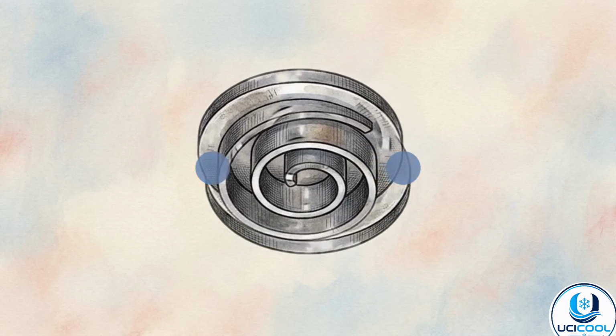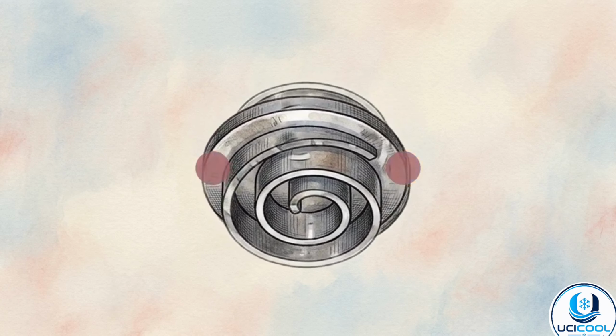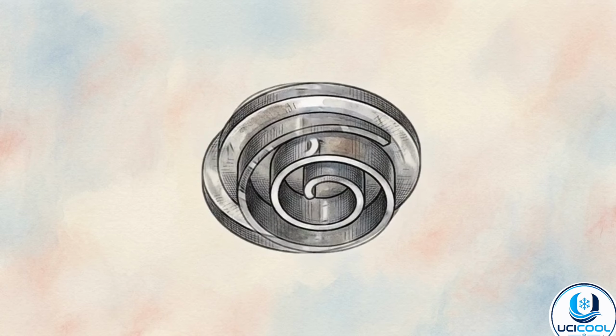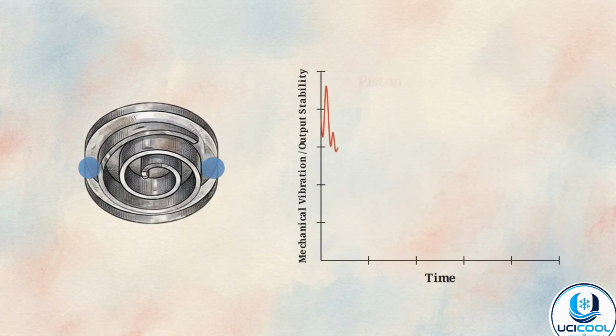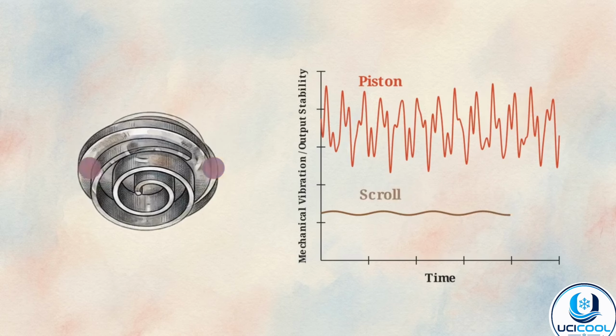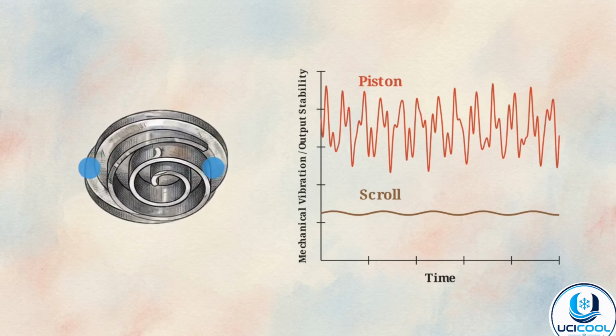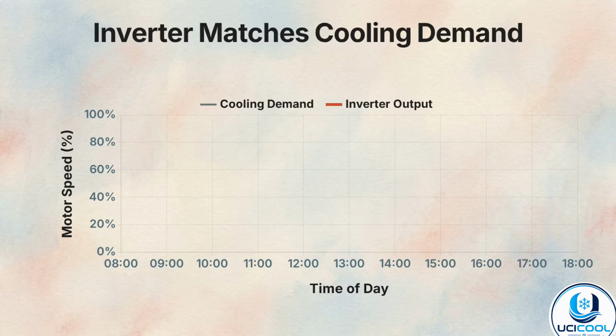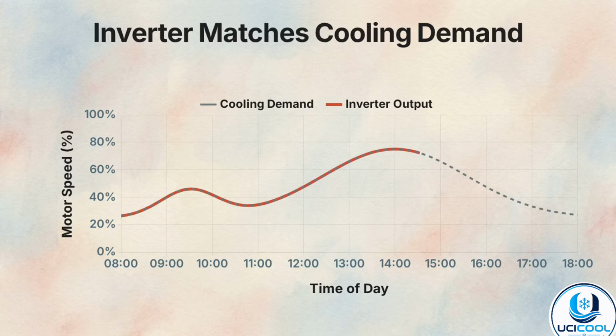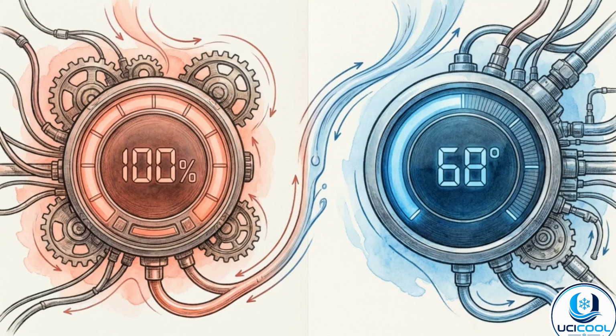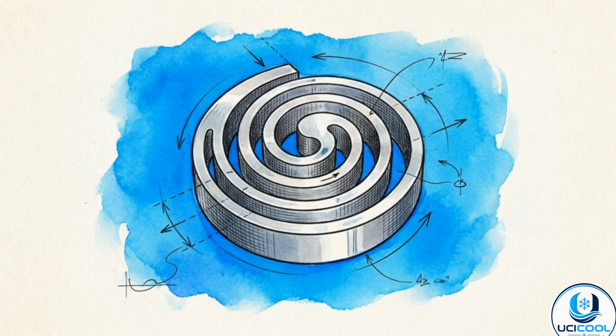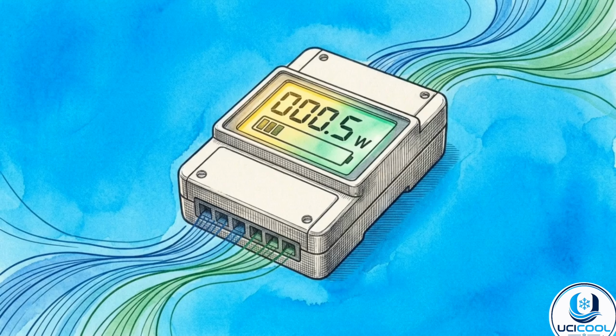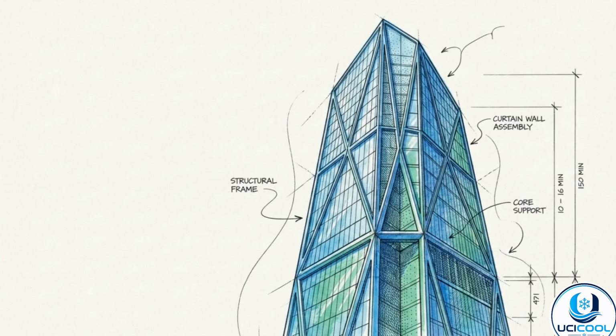The scroll compressor uses a different solution: two interlocking spiral scrolls. One remains stationary while the other orbits, continuously moving gas toward the center. This continuous motion eliminates the vibration of pistons, creating a smoother flow of refrigerant. These systems often utilize inverter technology, which allows the compressor motor to adjust its speed based on the cooling demand. Instead of a simple on-off cycle, the motor speeds up or slows down to maintain a precise temperature. Combining the smooth mechanics with variable speed motors provides the energy performance required for modern commercial buildings.